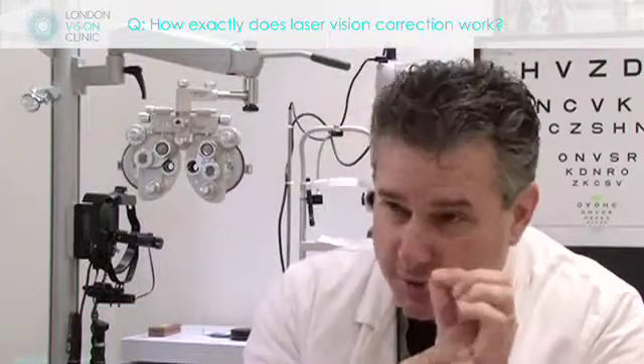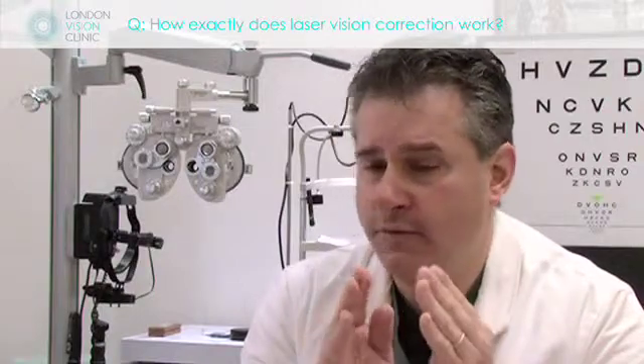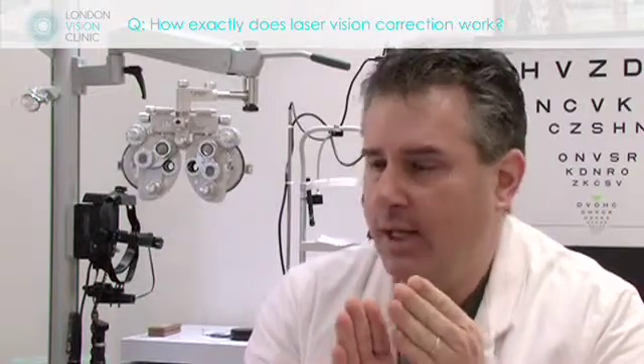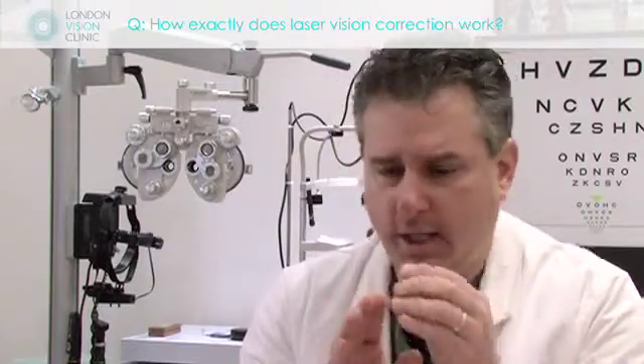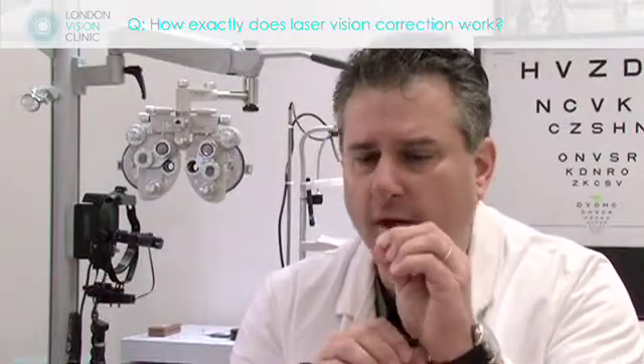The laser that is used is an ultraviolet light — specifically at 193 nanometers. It's a specific wavelength which is absorbed very, very efficiently by the cornea. Because the energy is absorbed so efficiently, it doesn't penetrate, meaning all of the energy in a pulse is taken up by the front quarter of a thousandth of a millimeter of tissue.